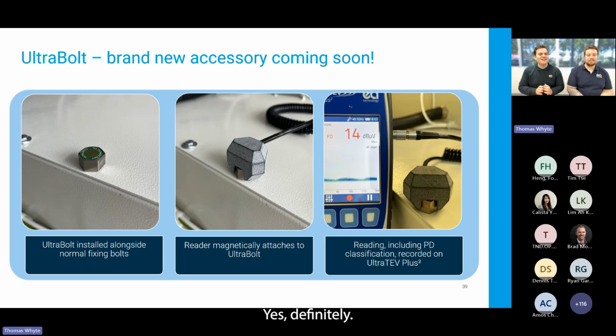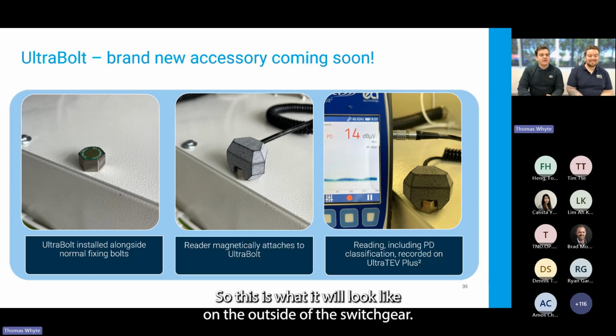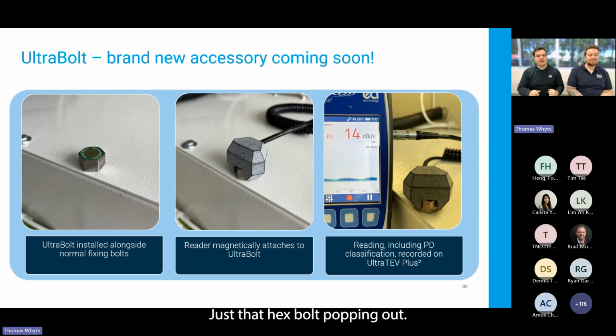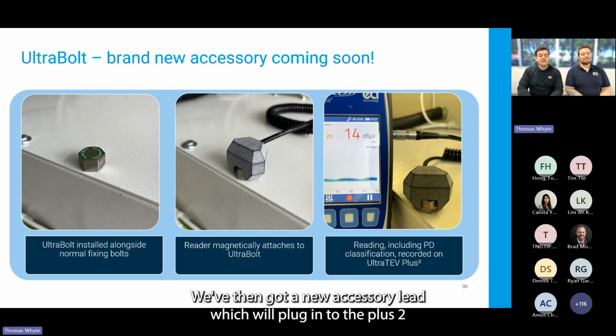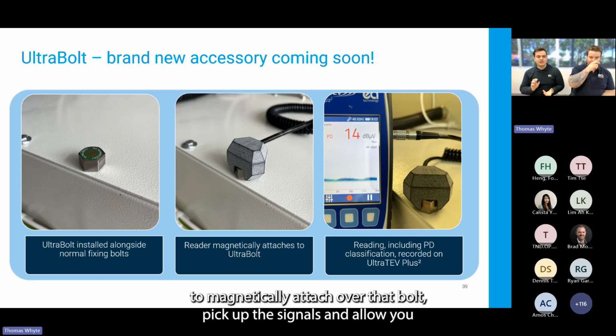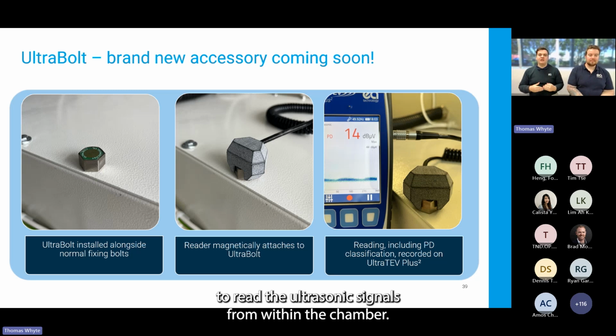Yes, definitely skewing my own poll there. But this is what you can see right here - this is what it will look like on the outside of the switchgear, just that hex bolt popping out. We've then got a new accessory lead which will plug into the Plus 2, magnetically attach over that bolt, pick up the signals, and allow you to read the ultrasonic signals from within the chamber.